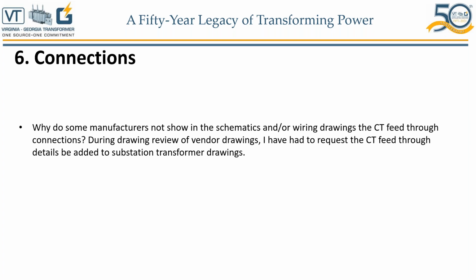Okay, and then when you receive the transformer, you connect to this control cabinet, to terminal blocks, and you do whatever you want to do with these CTs. Now let me answer the question after the explanation: why some manufacturers may not be giving this. Maybe the reason is that transformer suppliers know that when you receive the transformer, you will be connecting your CT outputs from the terminal blocks in the control cabinet. You're not going to have to go on top of the transformer or on the side top somewhere, wherever this feed through is. You're not going to need to make any connections there, okay? And the only connections you're going to make will be from the control cabinet.